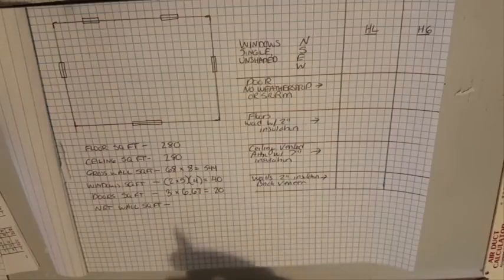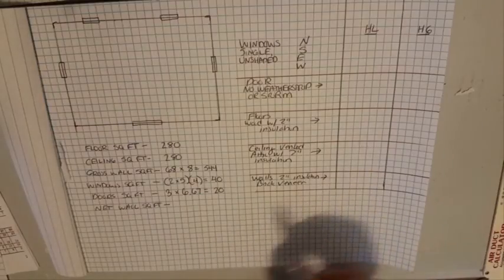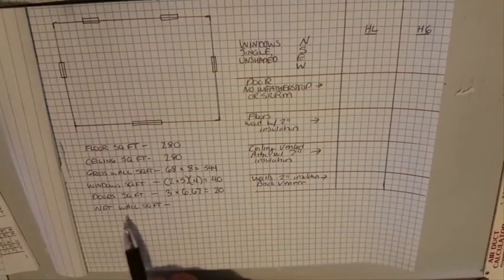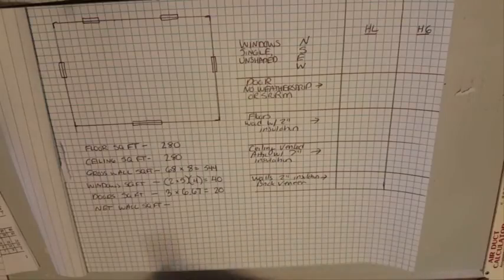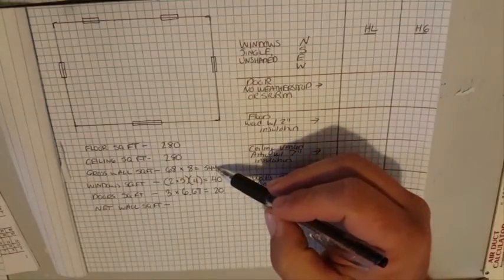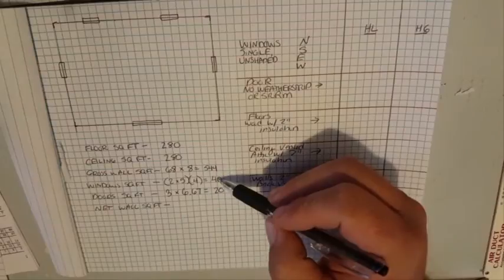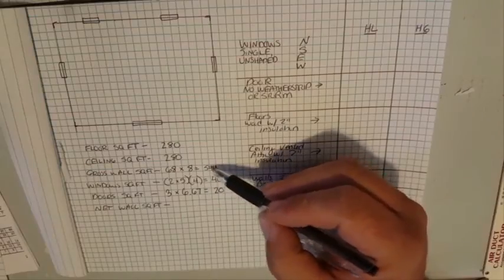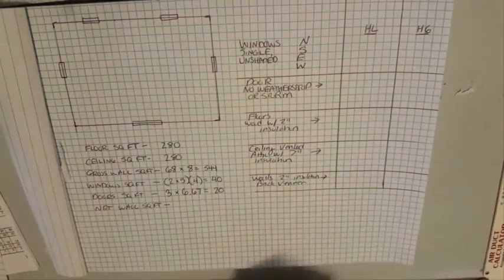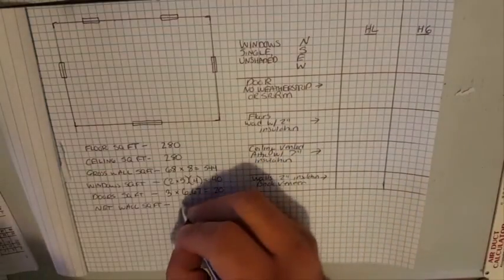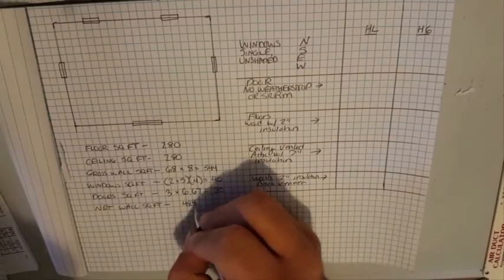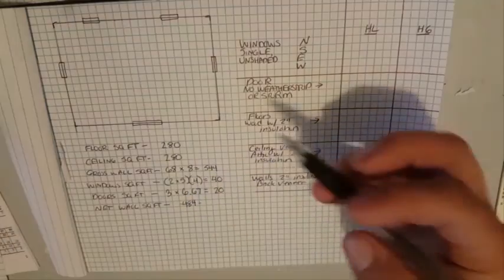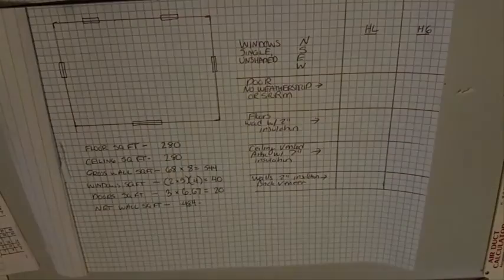So what we're going to take is net wall square foot, and we're going to take 544 and subtract 20, subtract 40, which is 504, another 20 which makes 484. So that is the actual wall square footage once we take all the doors and windows out of it.